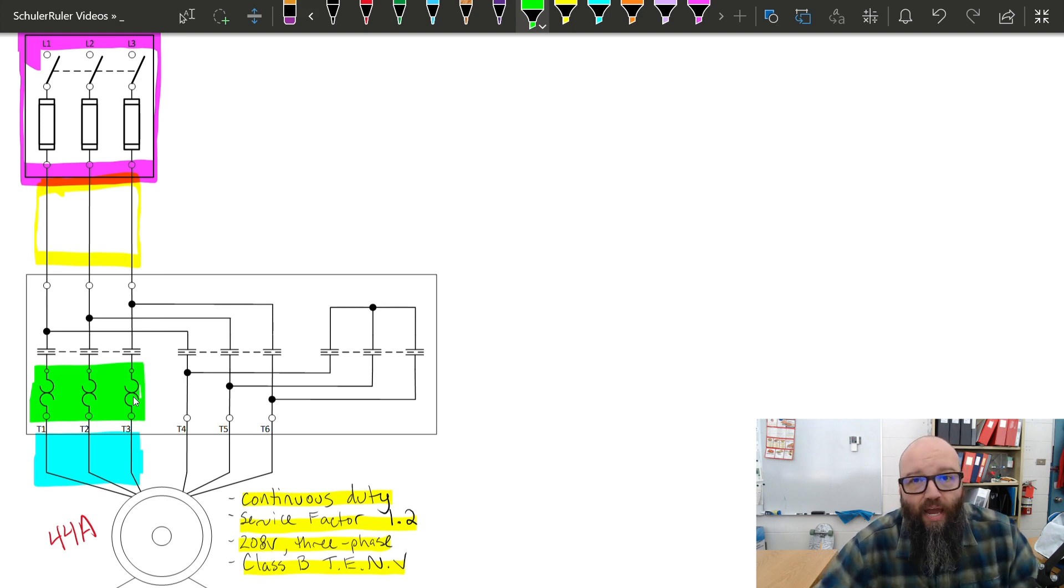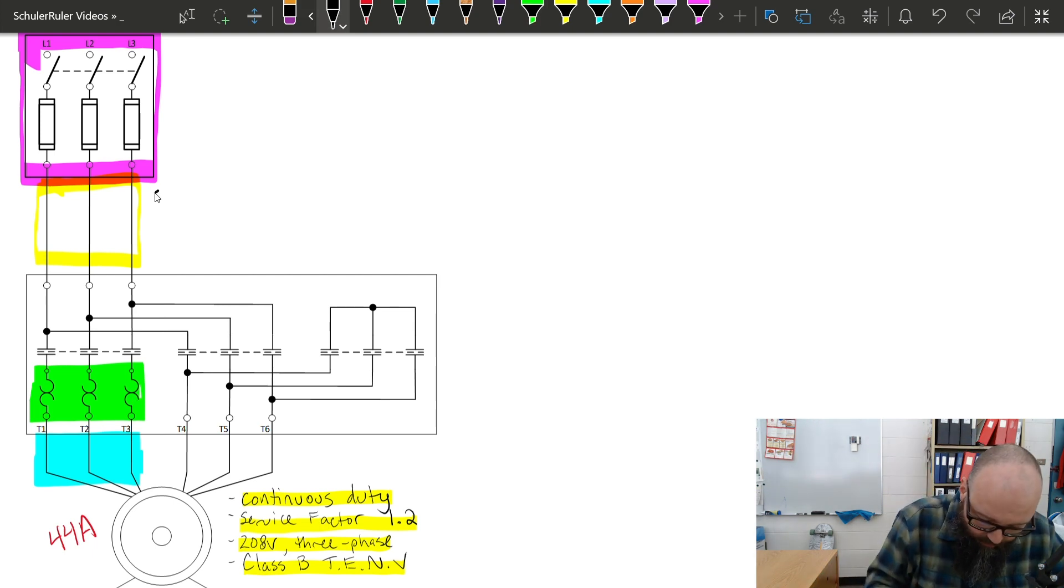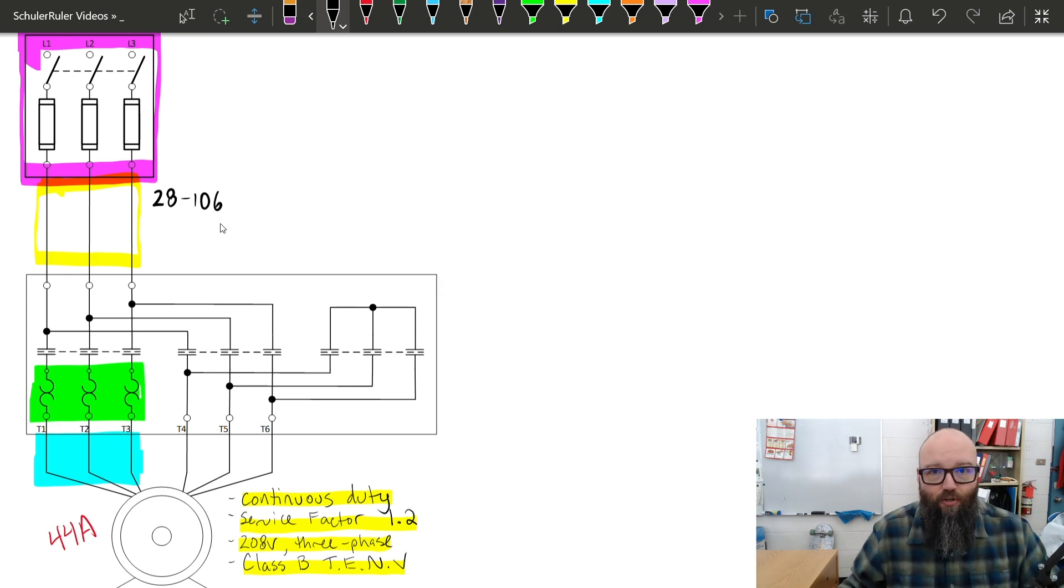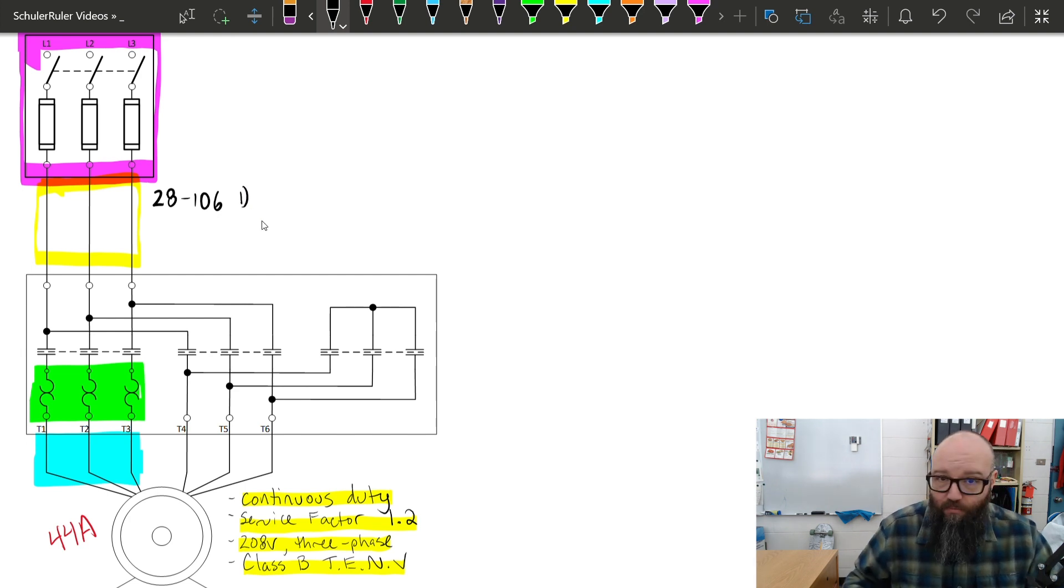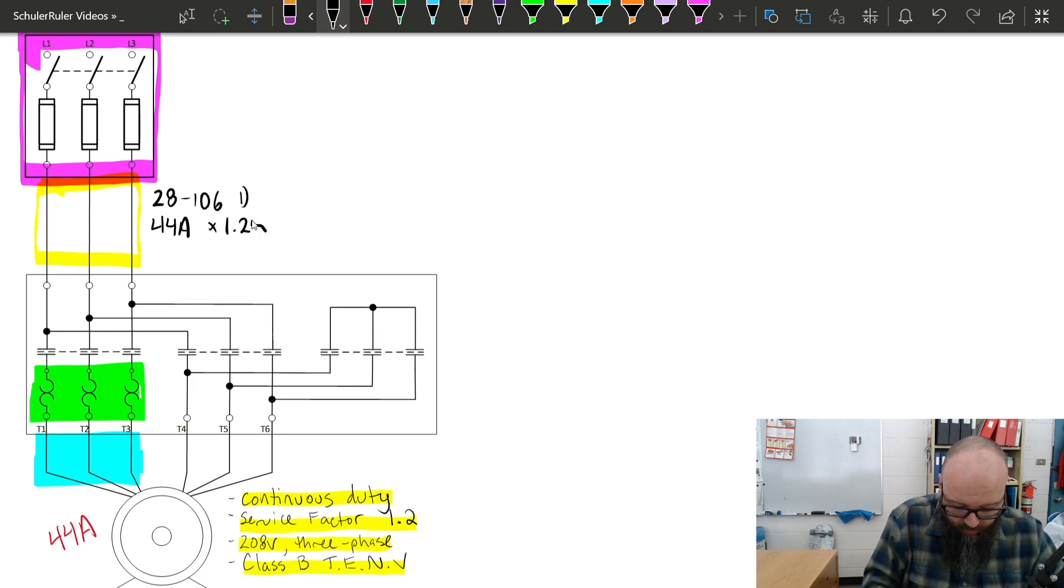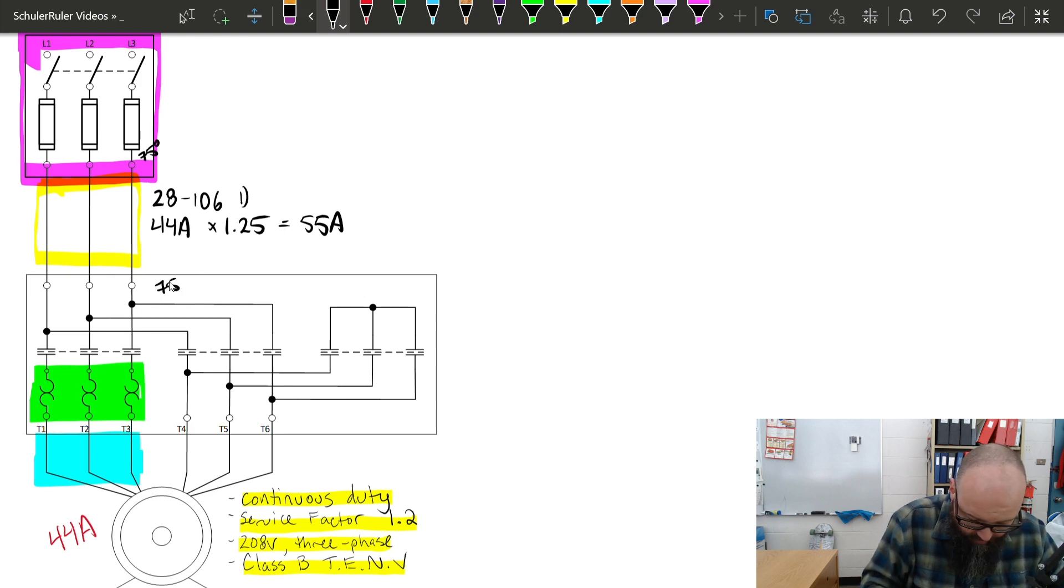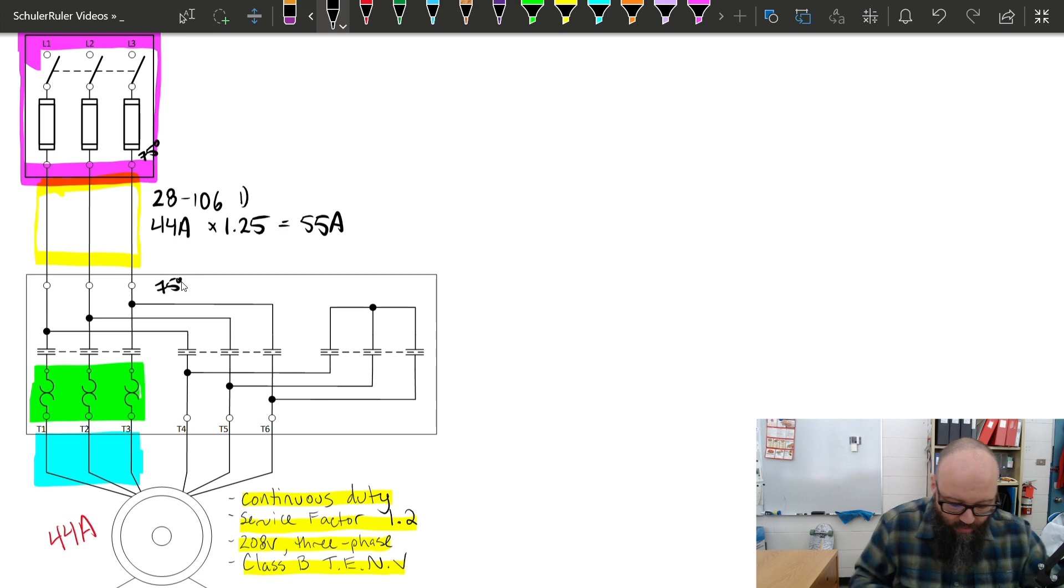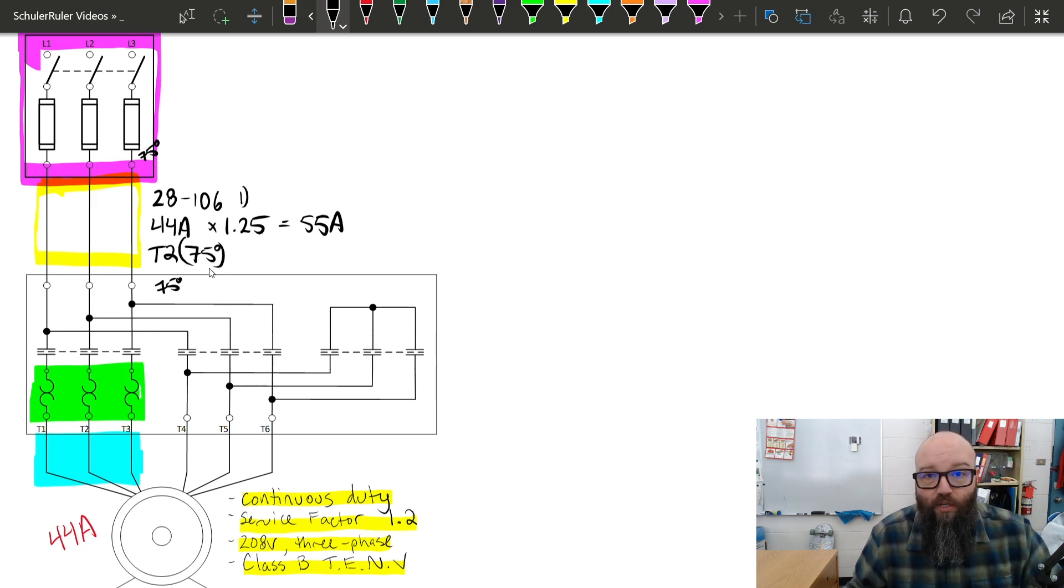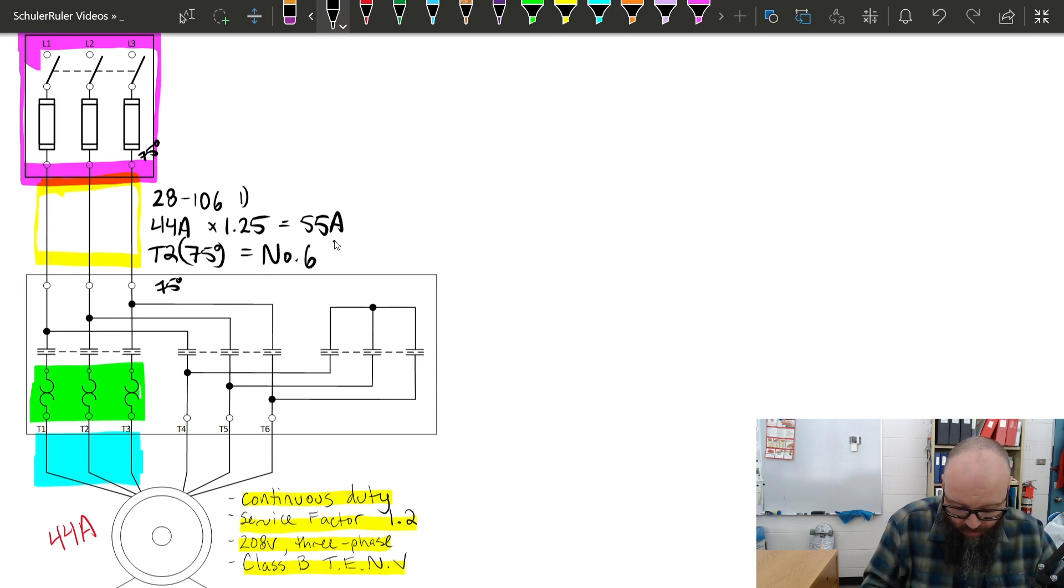Starting off with 28-106, because it is a motor branch circuit, and these are the branch circuit conductors. Because it's a continuous duty motor, we're going to start with subrule 1, which tells me we're going to take our FLA of 44 amps times 1.25 to get our minimum ampacity of 55 amps. We're going to put some termination temperatures. We're going to say 75 degrees in both our disconnect and our motor starter here, so that when we go to table 2, we're going to utilize that 75 degree column based off the requirements of 4-006, lowest termination temperature. We should see a number 6 for our branch circuit with an ampacity of 65 amps.